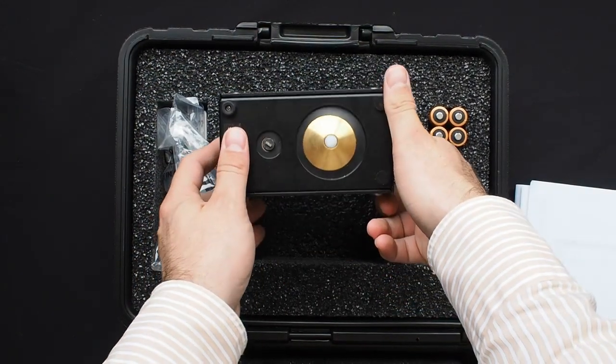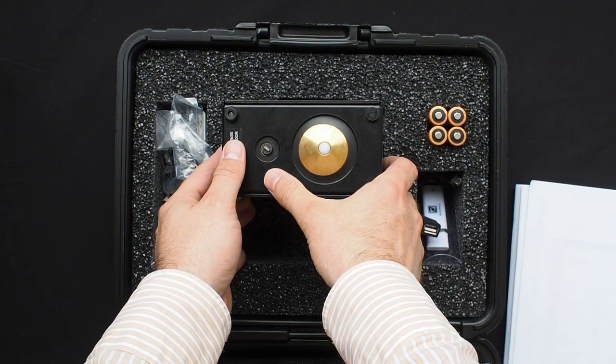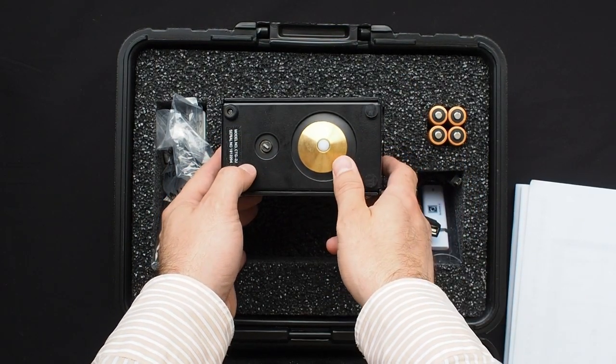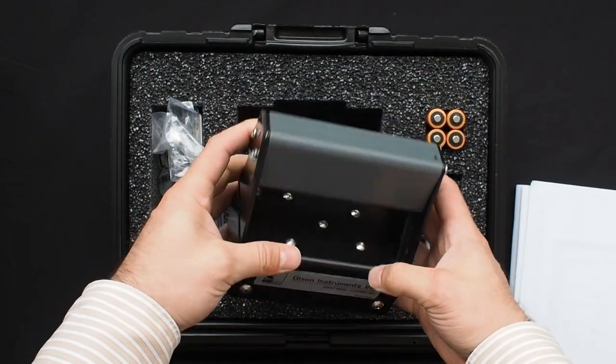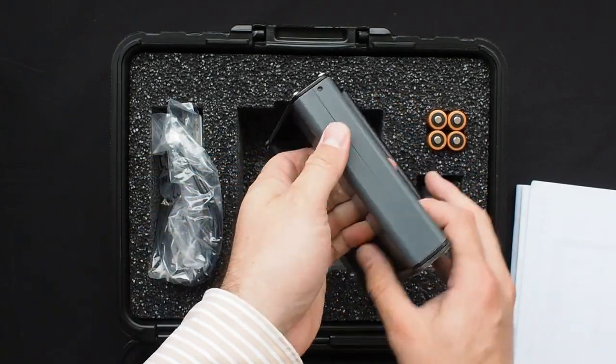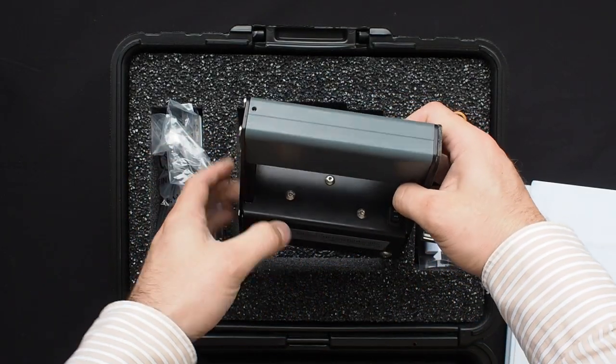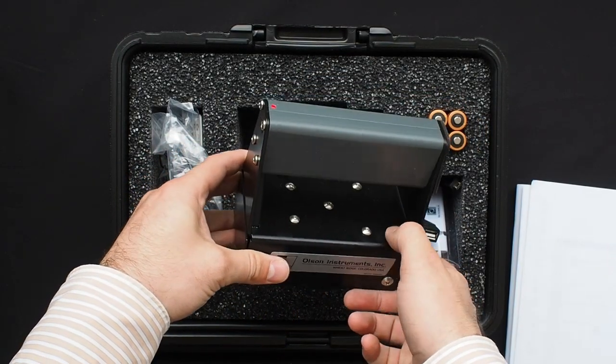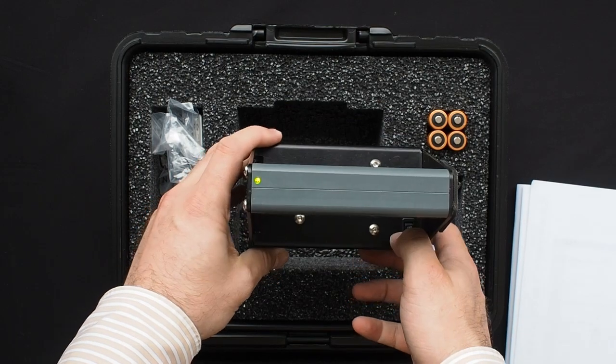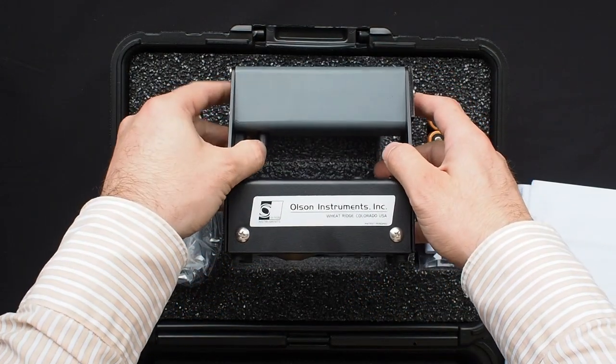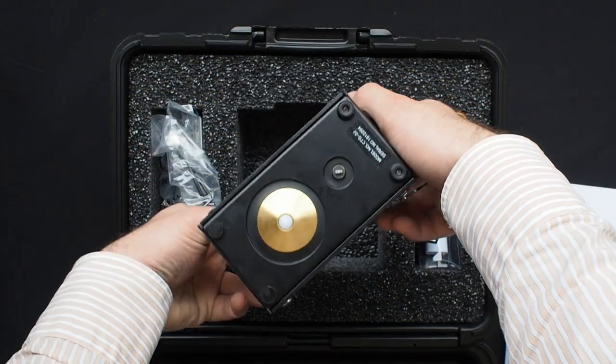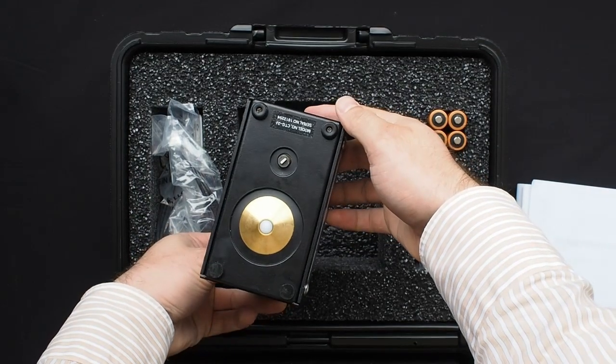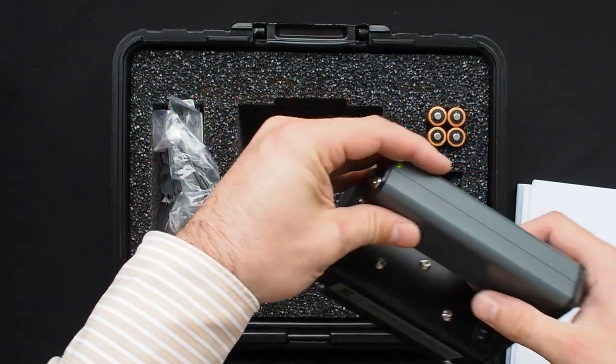The key components of the Concrete Thickness Gauge are the sensor, which is the white button, and the impactor, which is the left solenoid. There is a small light on top, and if we click the power on with the switch on the bottom right, it will go green if there's a sufficient battery, and this is the switch for firing the impactor, as you can see here.